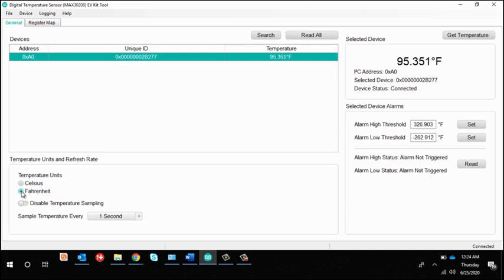This depends on the use case and the location on the body. You can notice that my temperature reading is a little low and it is important to note that we are measuring skin temperature, not the core temperature.